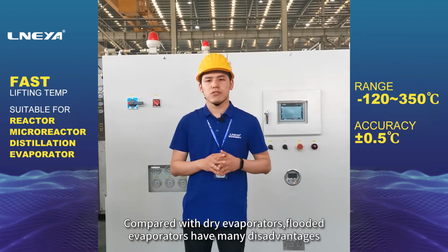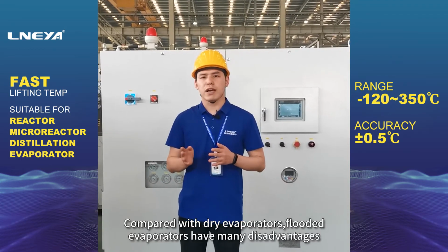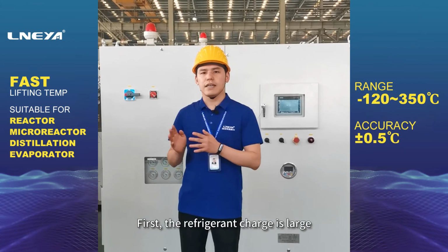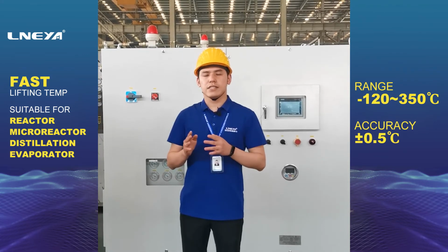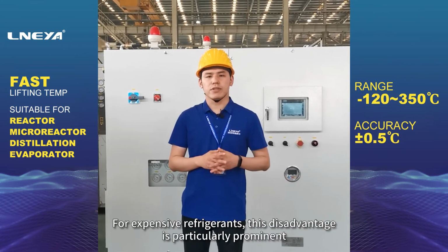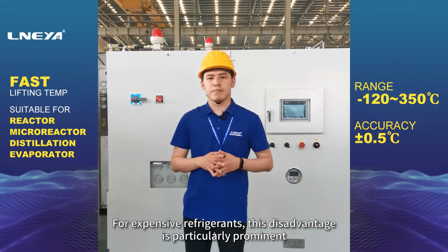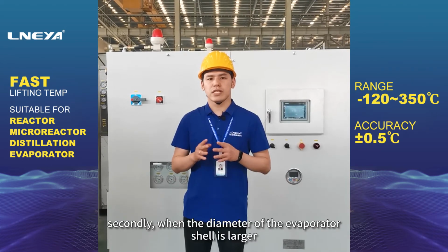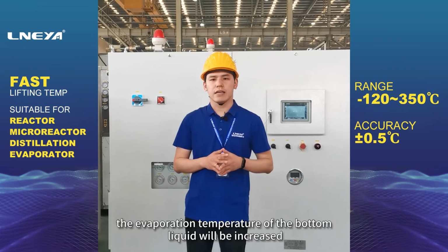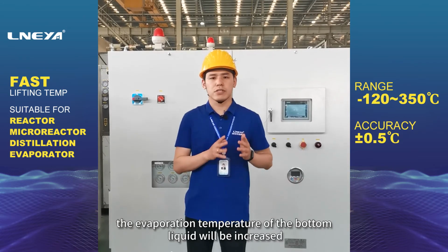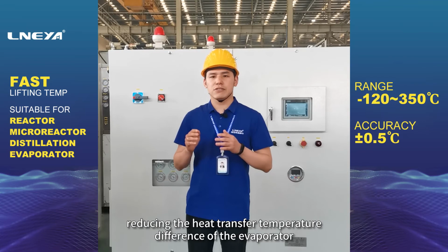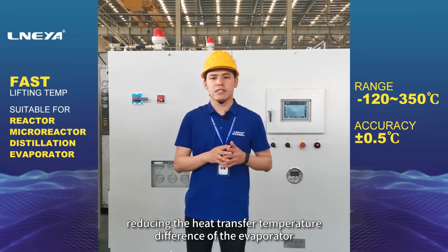Compared with dry evaporators, flooded evaporators have many disadvantages. First, the refrigerant charge is large. For expensive refrigerants, this disadvantage is particularly prominent. Secondly, when the diameter of the evaporator shell is larger, the evaporation temperature of the bottom liquid will be increased, reducing the heat transfer temperature difference of the evaporator.